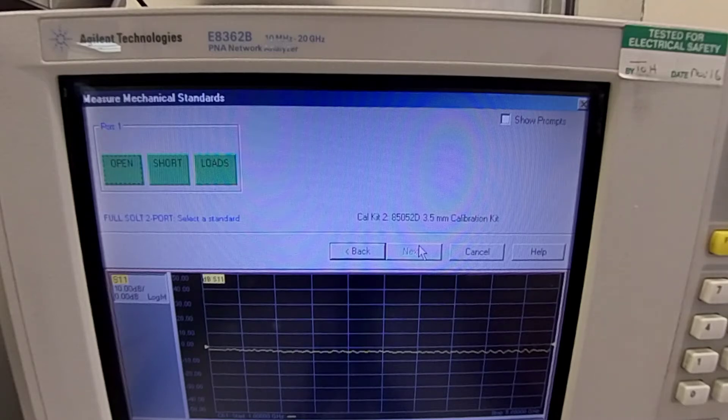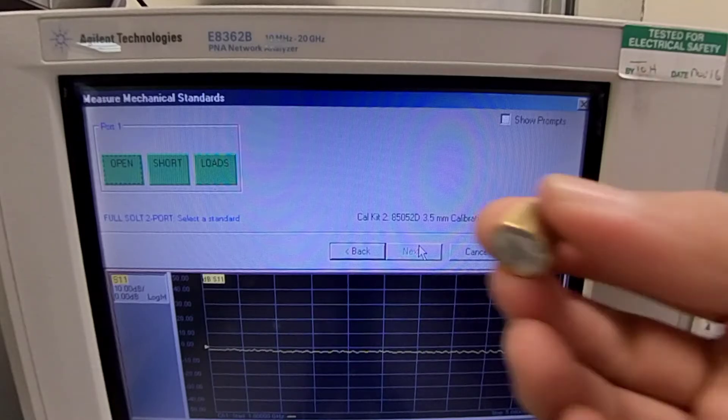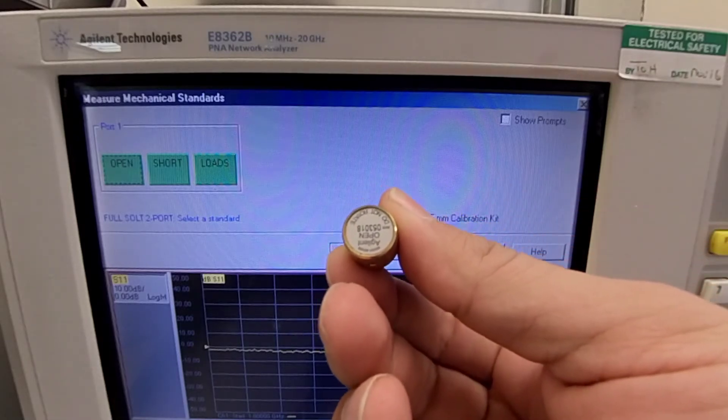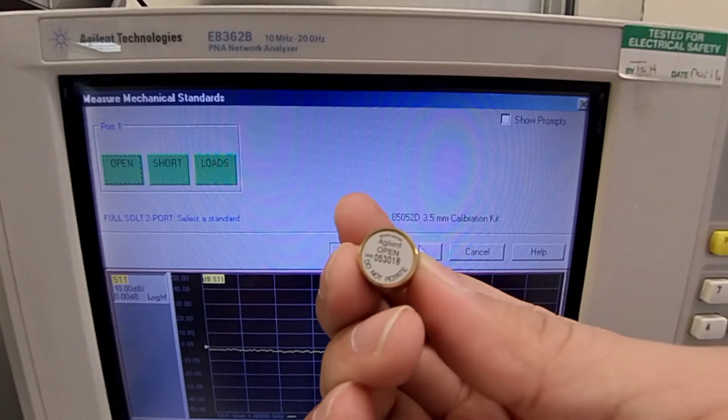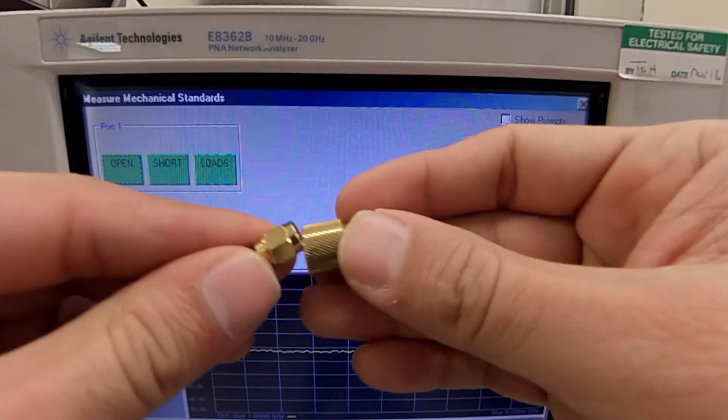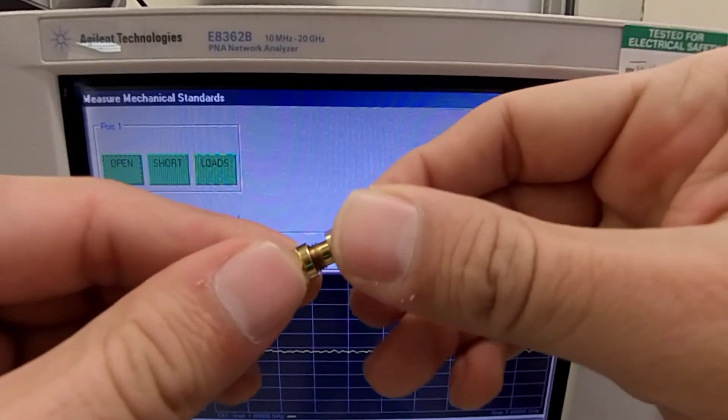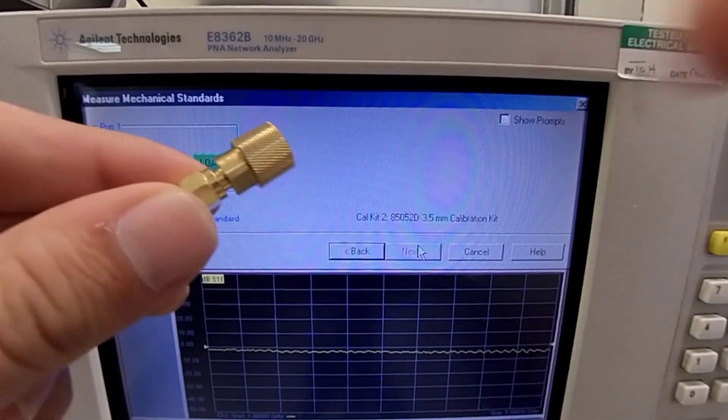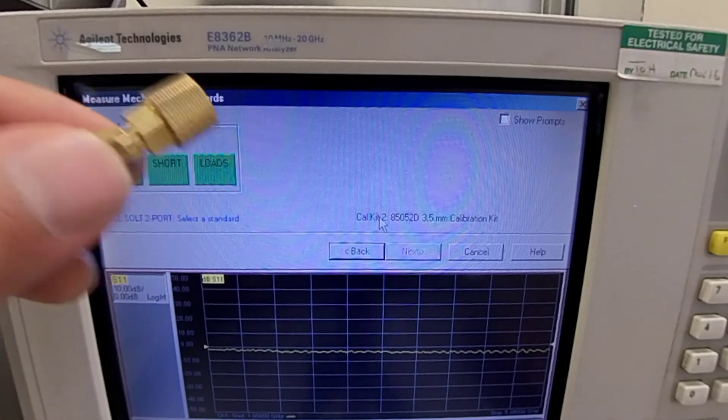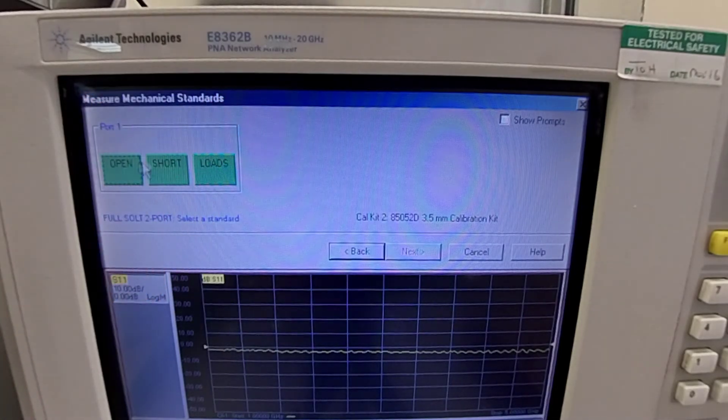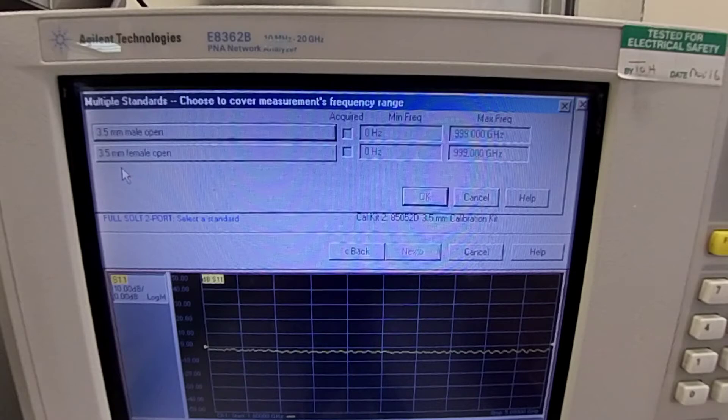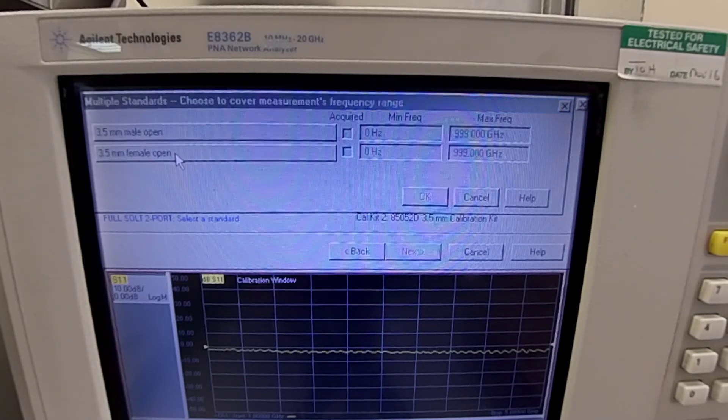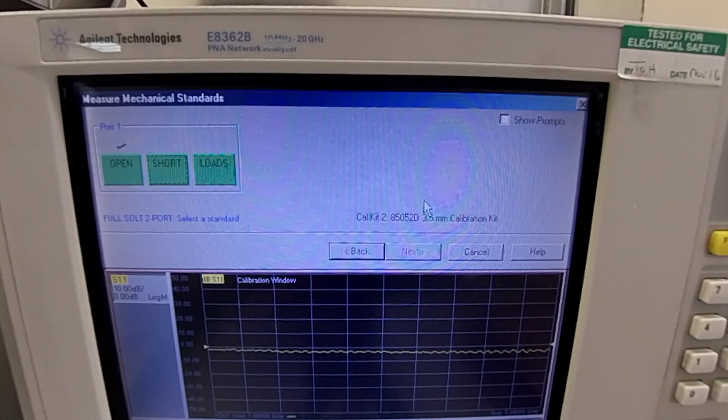Click next. And now we need to connect an open load as you can see. This is an open. And we will select connect the open as a load. Click on open. The connector we are using is 3.5 mm female. Select. Press OK. And now we are done.